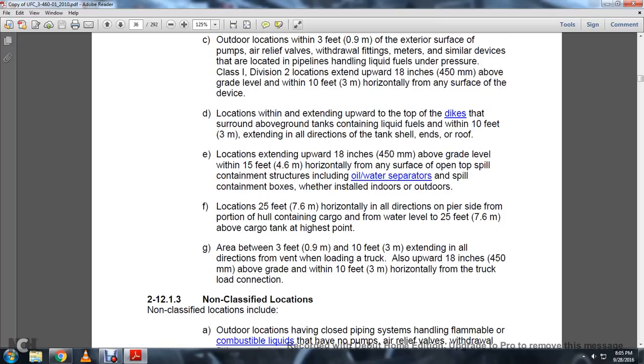Location: 25 feet horizontally in all directions on the pier, aside from the portion of the hull containing the cargo, from the water level to 25 feet above the cargo tank. The highest point areas between 3 feet and 10 feet extending in all directions from the vent when loading the truck. Also upward 18 inches above the grade and within 10 feet horizontal from the truck load connection.